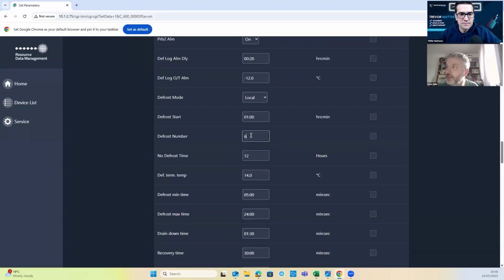Worth noting, defrost number, different to some manufacturers, is not how many hours between defrosts. It's how many defrosts per day, right? Some manufacturers say defrost hours or defrost interval, 6 hours, let's say. Carel's a good example. Carel says defrost interval. If you set it for 6, it'll be 6 hours between defrosts. If you set defrost number for 6, you'll get 6 defrosts a day. Okay? And no defrost time is usually for when you're doing a remote signal.